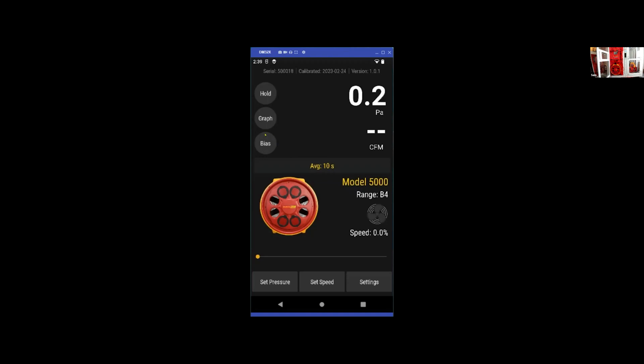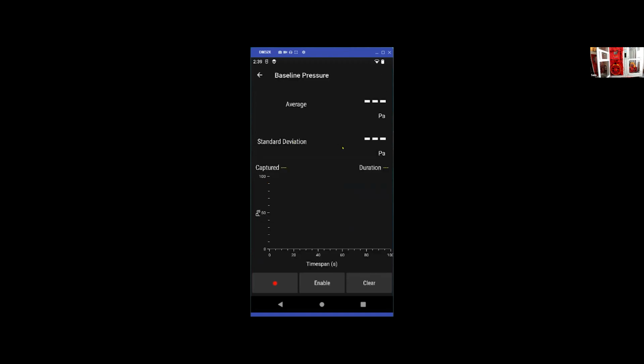We have a button here under the graph that says bias, and that's where we'll go whenever we want to take that baseline reading. There's a little record button we can press, and it'll go ahead and start graphing that out for us, and we can actually see that visually displayed there. If I simulate some wind happening, that's what our baseline readings will look like. We can see that duration counting down—we've been going for about 15 seconds now—and we can see the average we're reading on channel A.